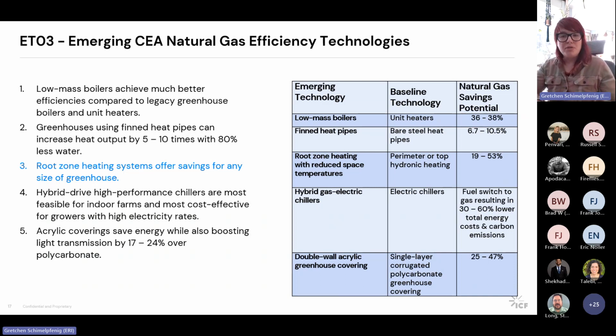Root zone heating. It's been around for a while, but is not widely adopted. Many growers choose to heat the greenhouse. They heat the space. They don't heat the plants. So a great efficiency measure would be to heat the plants directly and reduce space temperatures of the greenhouse. So the unit heaters and the boilers are not running as often, or they're not running to as high a temperature. And so heating can be distributed on top, above the canopy, or along the sides of the greenhouse. And instead of doing that, moving the heating distribution to mats with hydronic piping so that the benches are heated directly under the plants, or other sorts of perhaps underbench finned heat pipes, that can result in 19 to 53% annual energy savings when compared to top or perimeter heating.